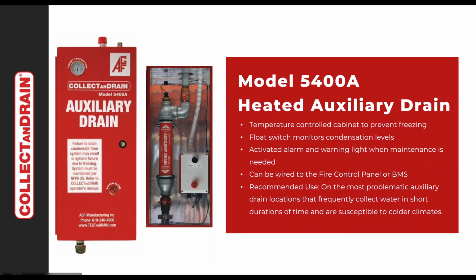So in this case, we've brought a heated environment to the low point drain so that they can't freeze and break. It also comes with dry contact, so it can alert your building management system or your fire alarm that the low point drain is now full. And it may take years for that unit to fill up. So you're saving a lot of time and aggravation going around and checking the low point drains all winter long by just having a simple cabinet.